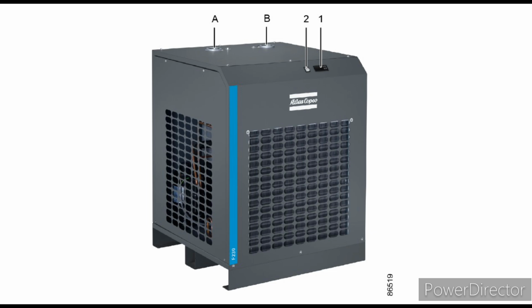So how does a refrigerated air dryer work? It operates on a principle similar to domestic refrigerators or home air conditioning systems. The compressed air is cooled in an air-to-refrigerant heat exchanger to about 35 degrees Fahrenheit, a temperature where the moisture condenses and is drained off. An air-to-air heat exchanger is used both to pre-cool the incoming air and to reheat the outgoing air as it leaves. The compressed air leaving the dryer has a pressure dew point of 35 to 50. So this is the working principle of the air dryer.